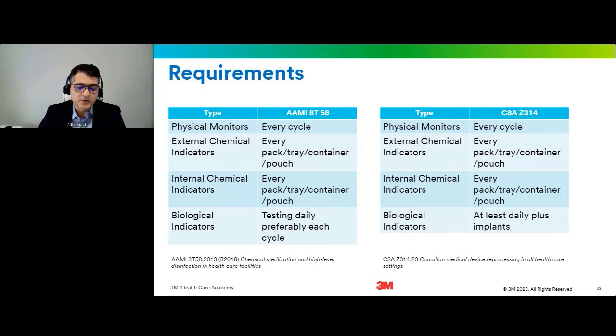This is a summary of monitoring requirements based on the standards. On the table on the left, you see the physical parameters and the documents, which ST58 recommends to have every cycle. External chemical indicators, every cycle, pack, container, or pouch. Internal chemical indicators, again, every cycle, pouch, pack, container. And biological indicators are recommended to be tested daily, preferably for each cycle. The column on the right side shows the frequency and requirements of monitoring for these physical, external, internal, and biological indicators from the CSA document, the Canadian Standards Association document Z314-23, which is actually a new document published recently.